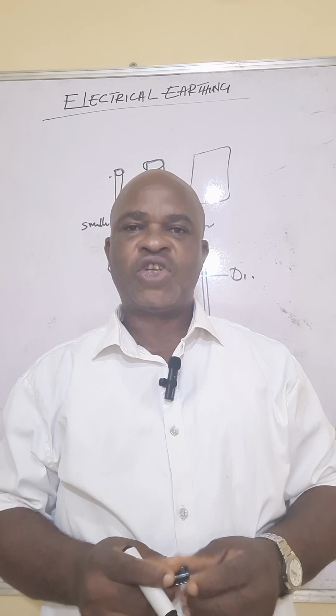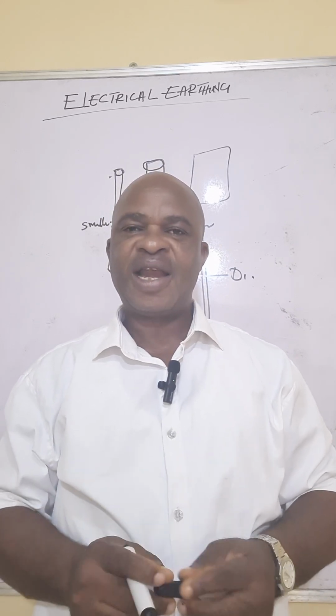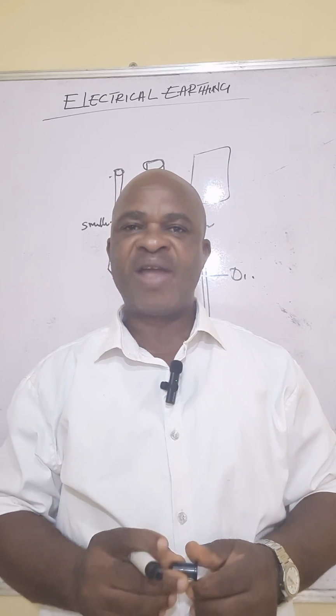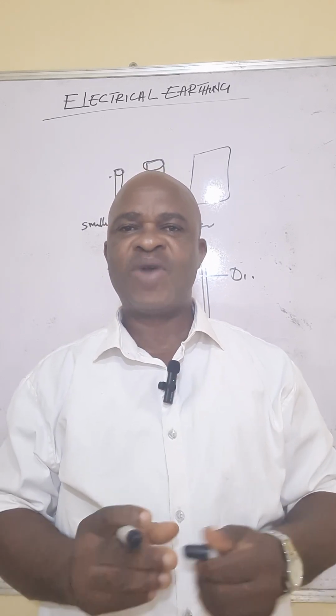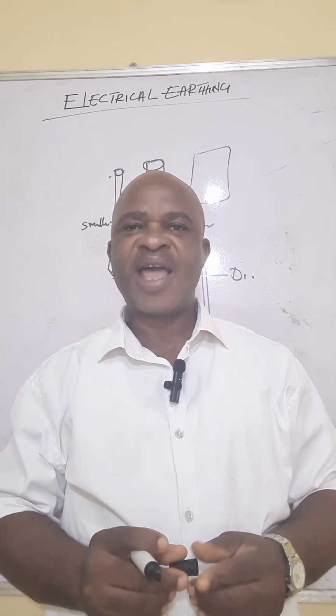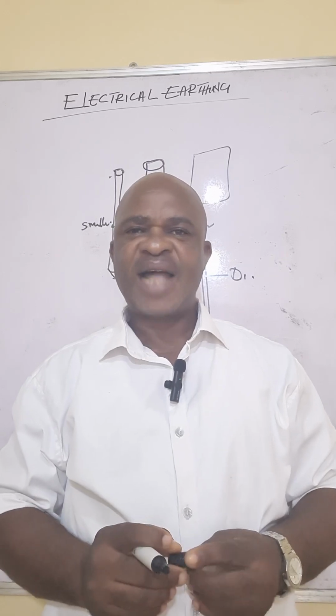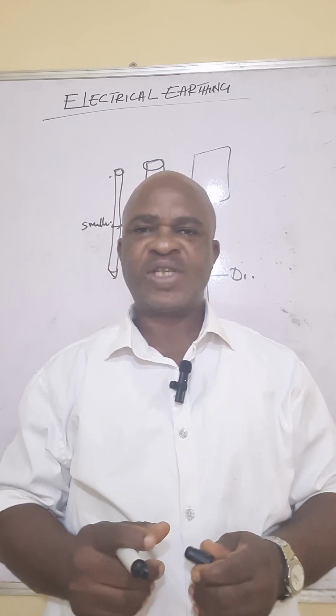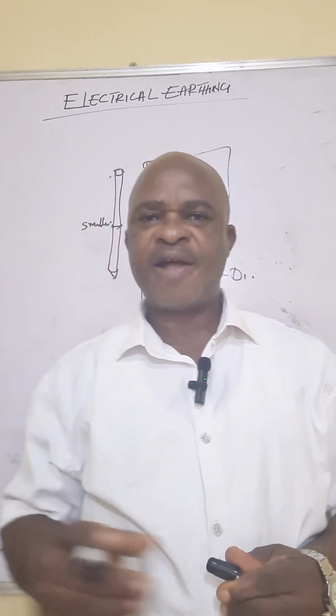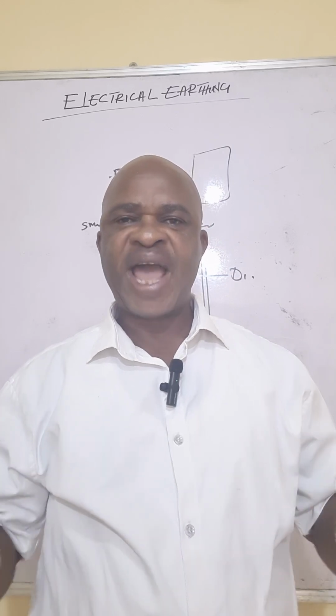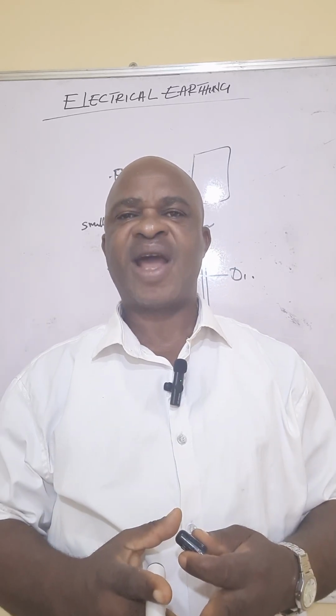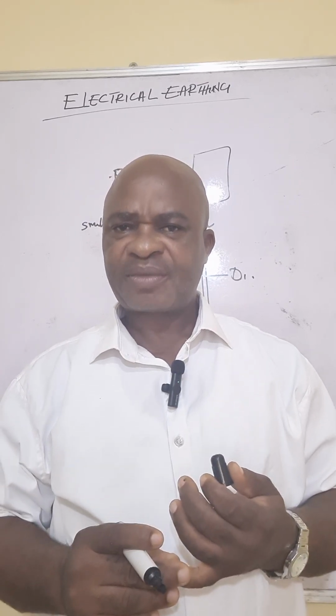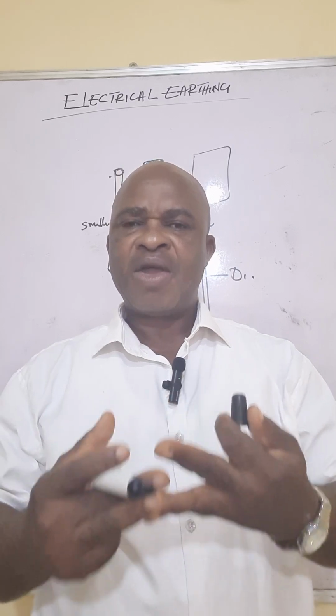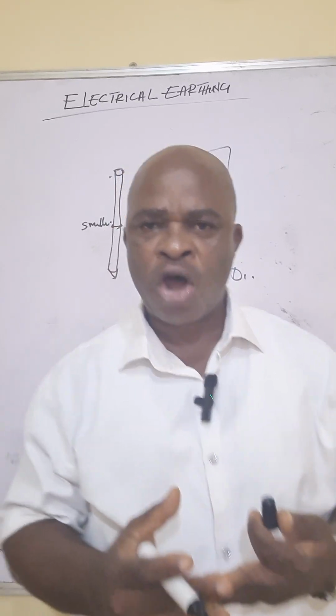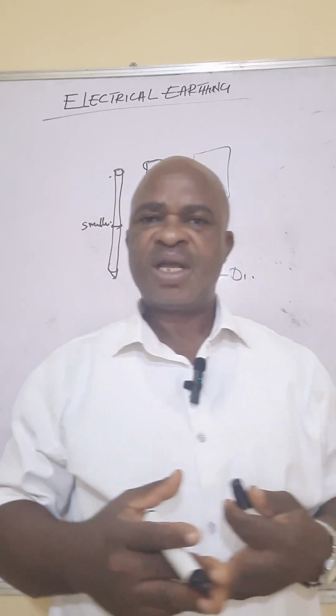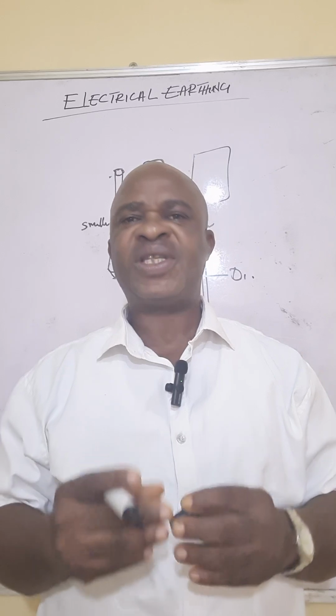I want to correct this notion. Most of us use industrial salt. I don't think that industrial salt is appropriate, my reason being that industrial salt will react with that electrode. I think it's high time electricians, engineers, artisans, and everybody involved in this field should start removing industrial salts whenever you are doing your earthing or incorporating earth treatment materials. If you use manure, soil, addition of human feces or goat droppings, poultry droppings, they are okay. They give you what you need. Salt reacts with the electrodes.